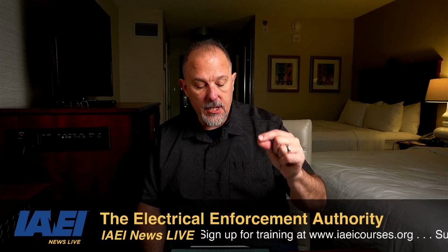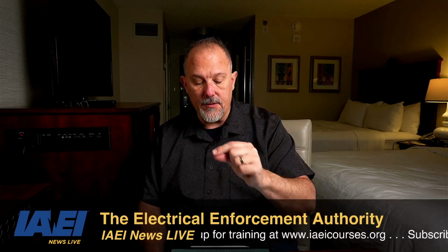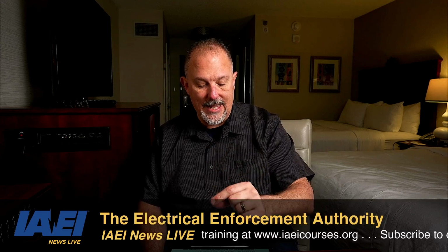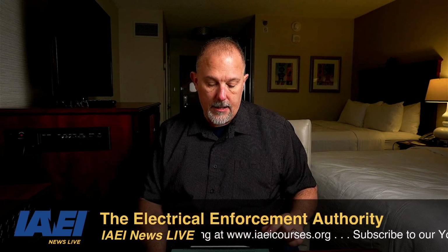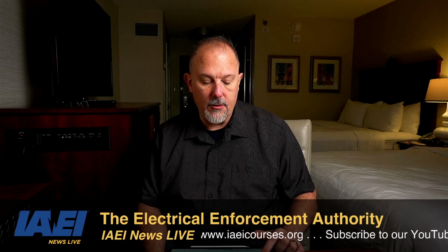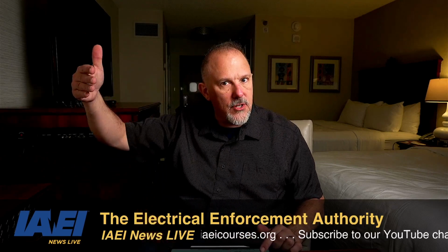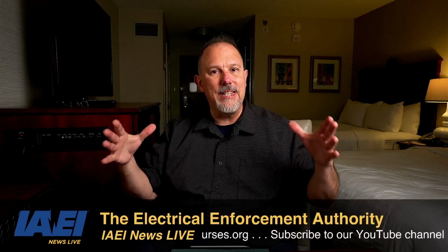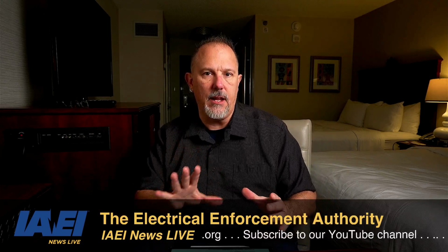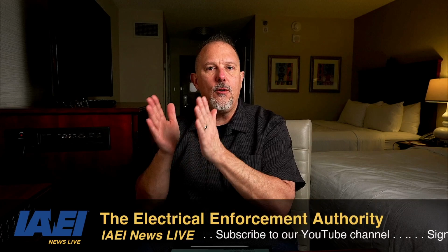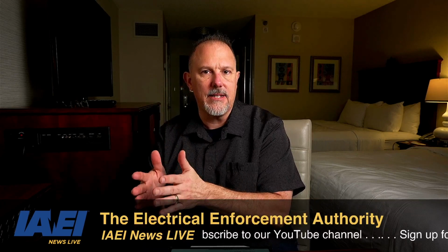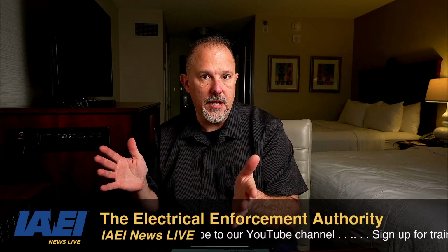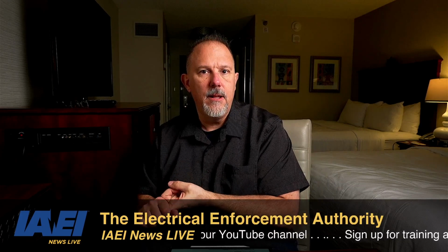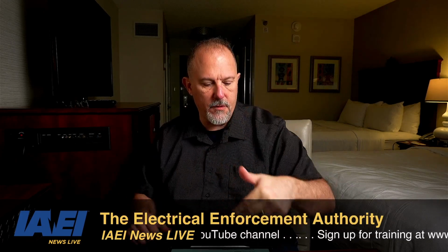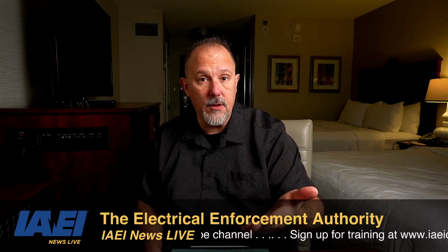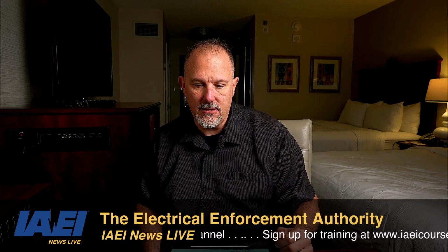And then an emergency shutdown device mounted on the exterior of the generator enclosure shall be permitted to satisfy the requirements of this section. The shutdown device shall be marked as the generator emergency shutdown. That goes back to that other discussion that we just had, that in some cases these generators have a disconnect built in. And as long as we label it correctly and we raise awareness of that disconnect, you can use that for a couple things now. One, to meet the requirement for the disconnect of the generator in general, and then boom, for the emergency disconnect. You're going to have to label it, though, as an emergency disconnect.